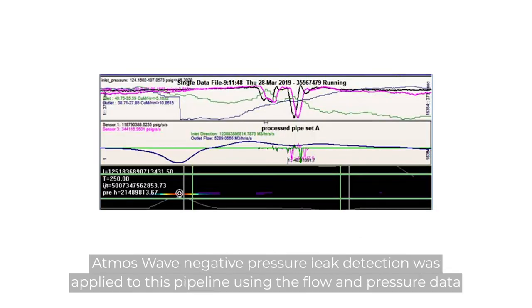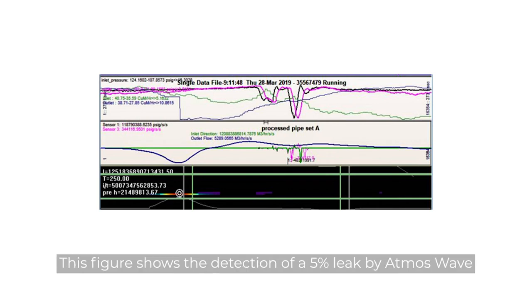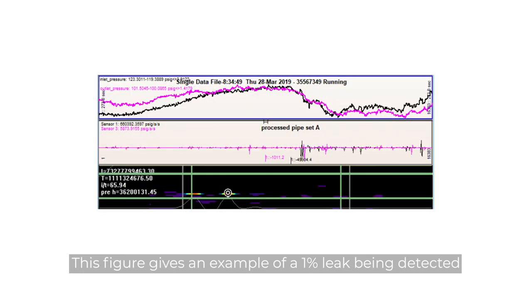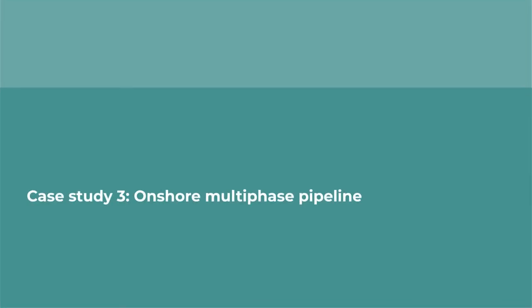Atmos Wave negative pressure leak detection was applied to this pipeline using the flow and pressure data. This figure shows the detection of a 5% leak by Atmos Wave. This figure gives an example of a 1% leak being detected.